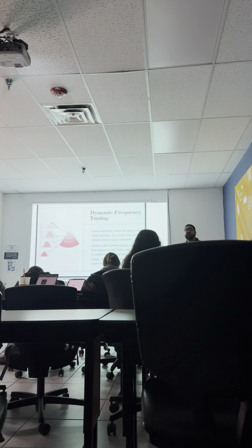Okay, so where do we want high frequencies? So what type of imaging? Superficial imaging, right? Okay, MSK, small parts, vascular, right? Okay, and where do we want low frequencies? Deeper structures, such as general abdomen, right? Okay, so with dynamic frequency tuning, we could actually pick and choose the frequencies that we use to make our image.